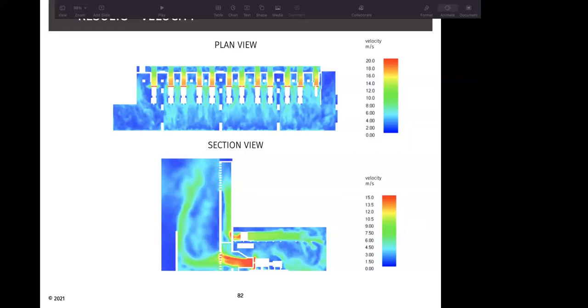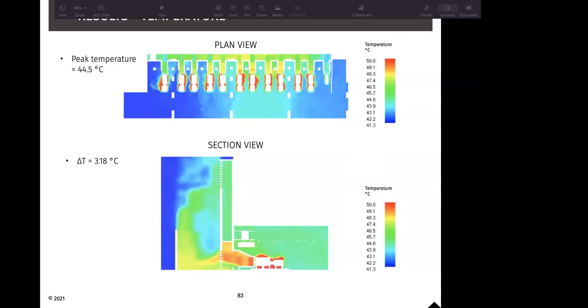So in the bottom section view, you can see that some amount of air is flowing back into the fresh air side. And there is some increase of temperature, especially in the center side of the room. So say, for instance, from DG number 5 to DG number 10, there is a rise in temperature around the DG set because this short cycling of hot air is happening. So the delta T in this case is 3.18 degrees centigrade. For a DG room, usually the delta T, considering the ambient condition, can be from 5 to 7 degrees. So that can then be studied by doing the analysis.